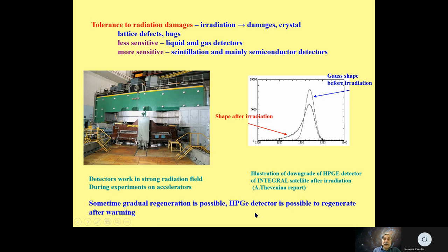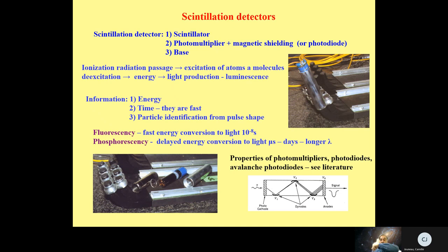Sometimes it is possible to have some gradual regeneration of the detector. It is also possible to regenerate a semiconductor detector by warming. Now we will look at different types of detectors, starting with scintillation detectors.